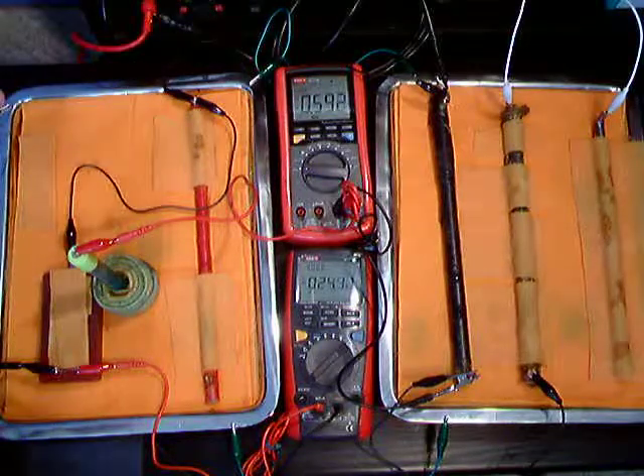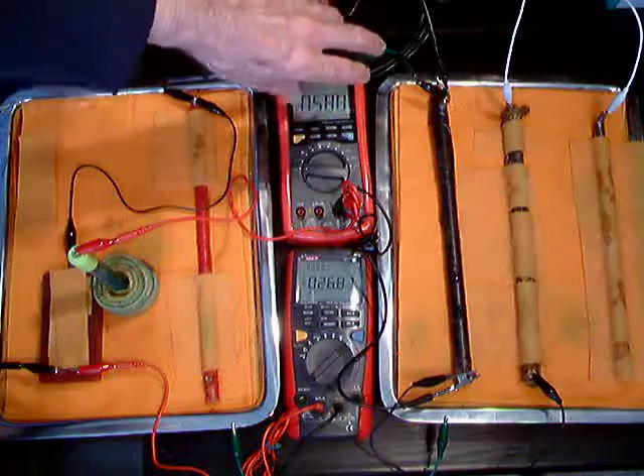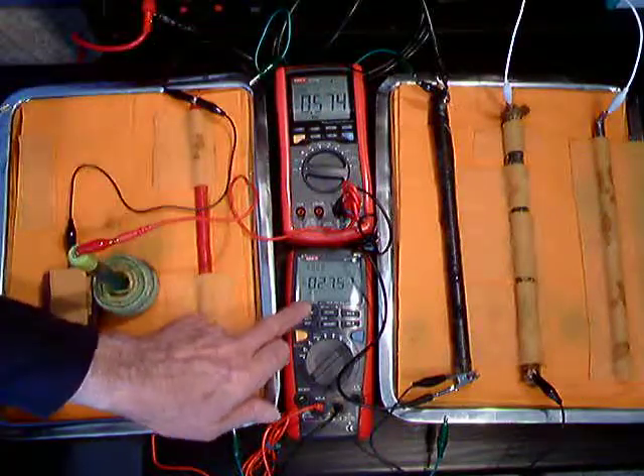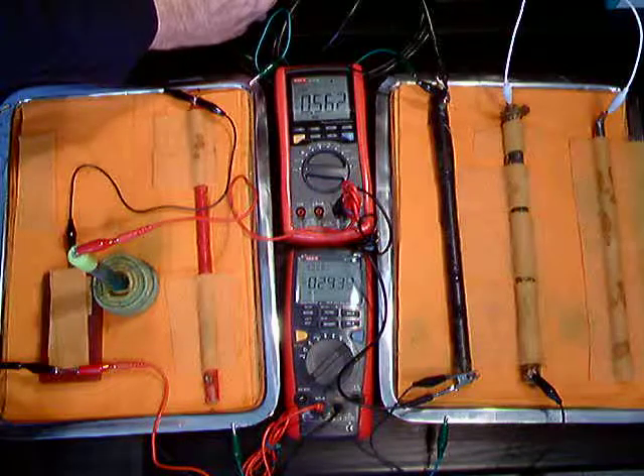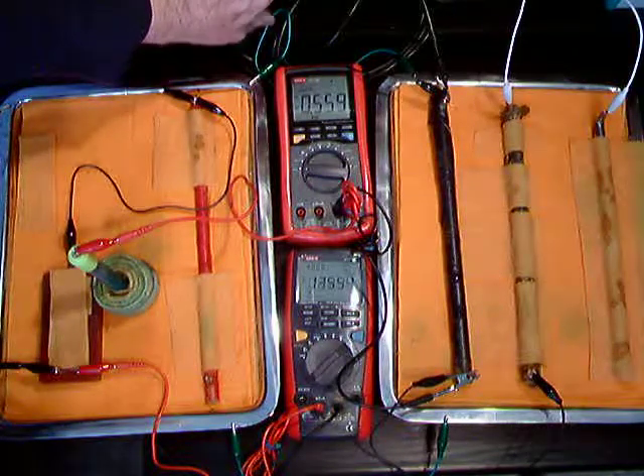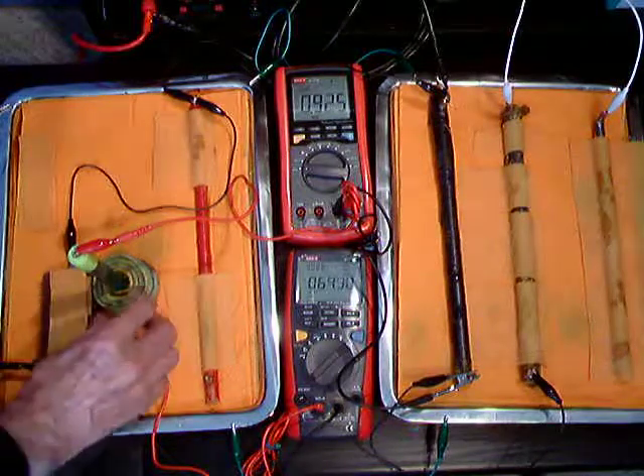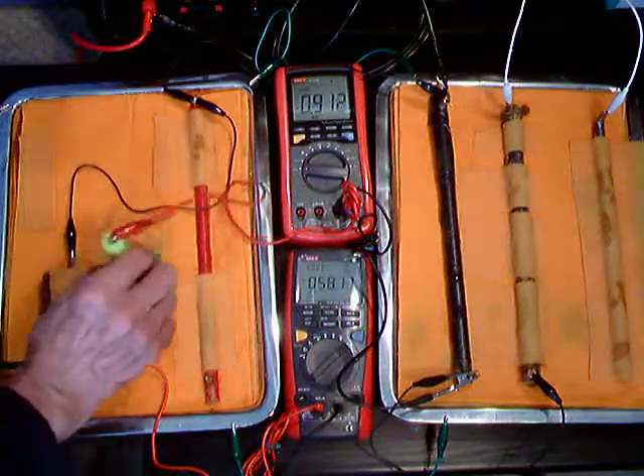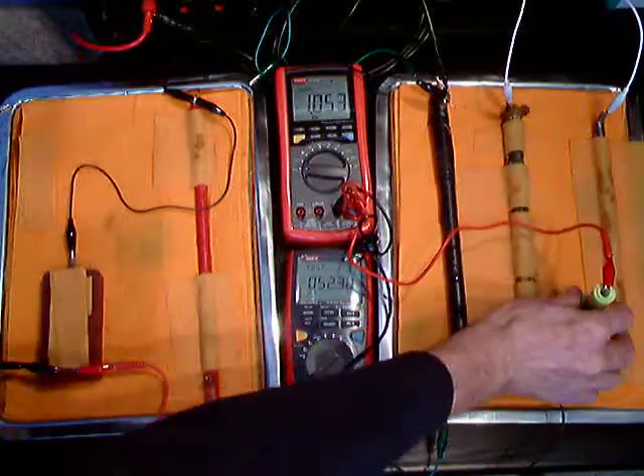This will gradually drop — it's what they call the off-potential depolarization. That is happening, but the corrosion is not continuing now, and the corrosion is stopped by the cathodic protection. The reading is considerably less than the measurement when it was taken in the other position over here.